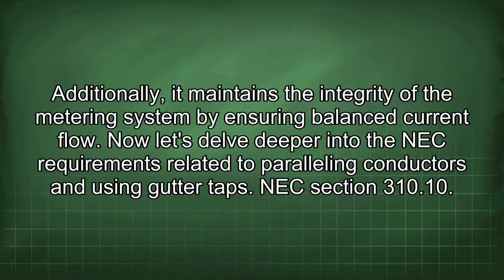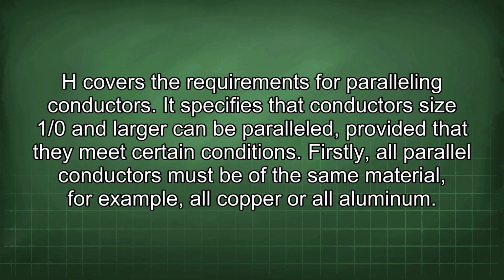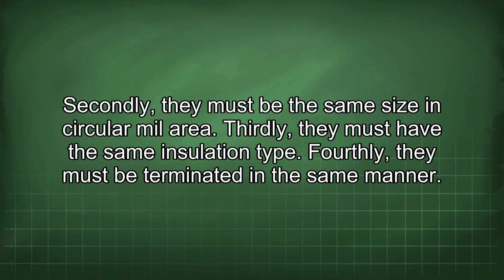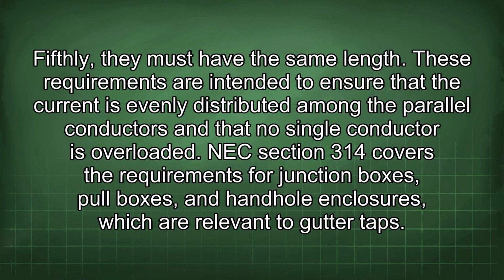NEC Section 310.10(H) covers the requirements for paralleling conductors. It specifies that conductors size 1/0 and larger can be paralleled, provided that they meet certain conditions. Firstly, all parallel conductors must be of the same material, for example, all copper or all aluminum. Secondly, they must be the same size and circular mil area. Thirdly, they must have the same insulation type. Fourthly, they must be terminated in the same manner. Fifthly, they must have the same length. These requirements are intended to ensure that the current is evenly distributed among the parallel conductors and that no single conductor is overloaded.